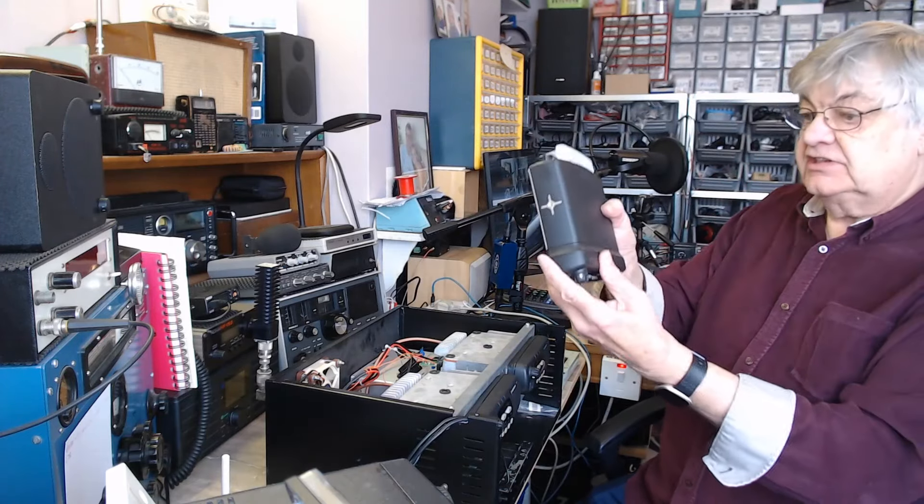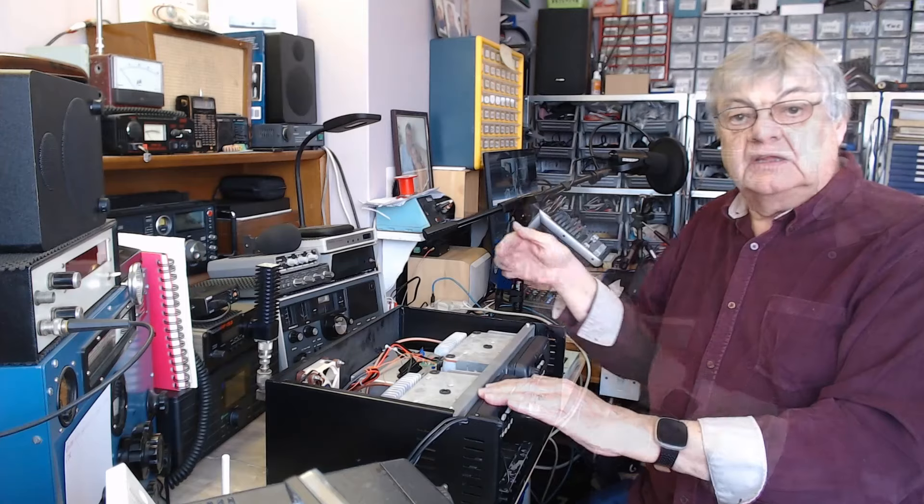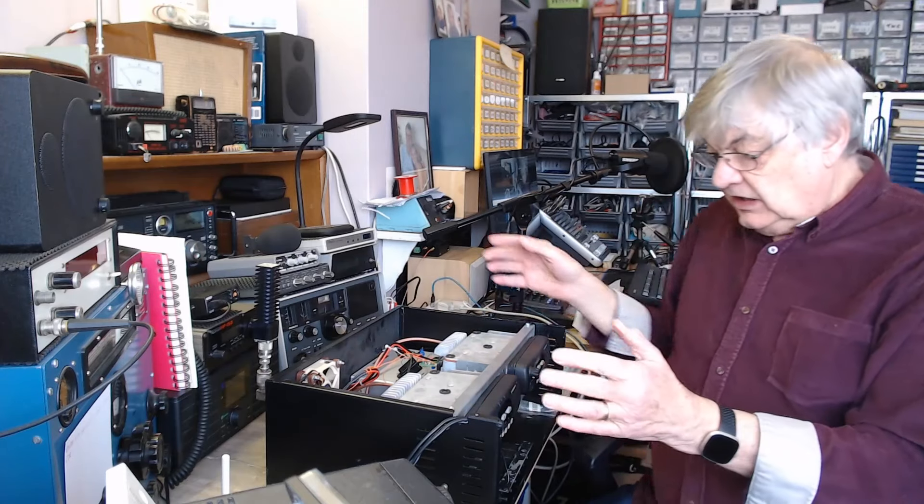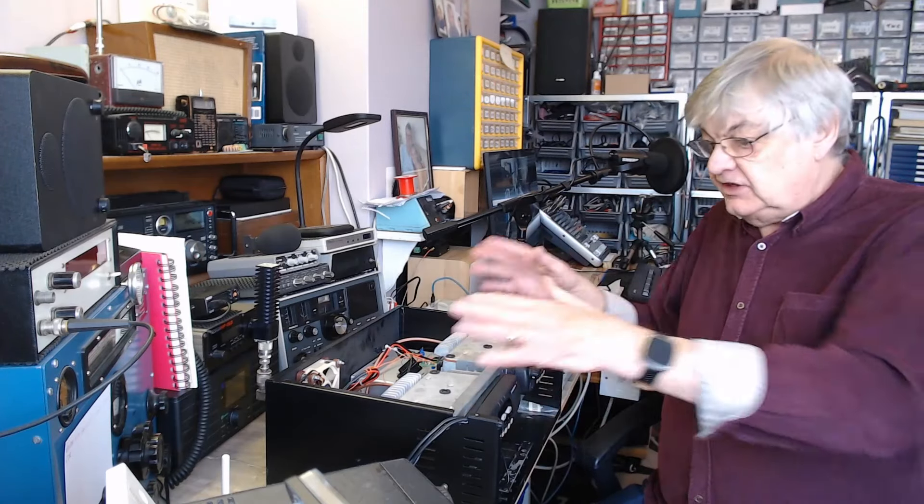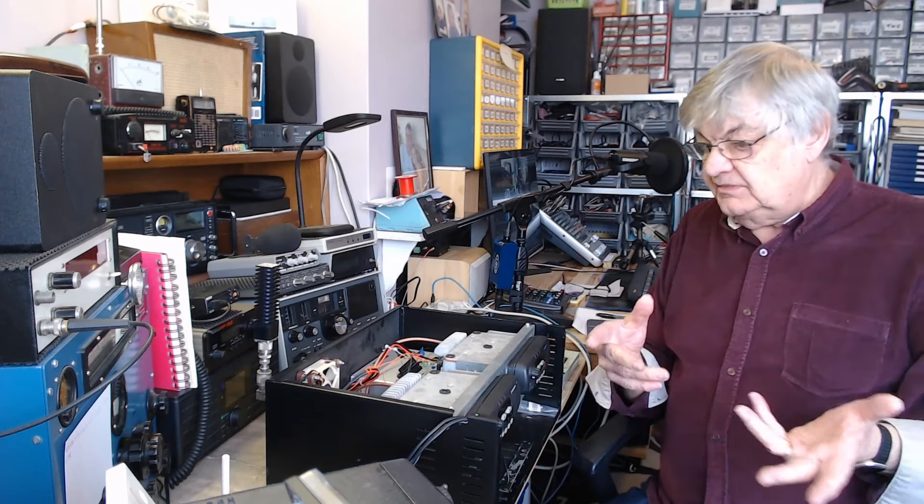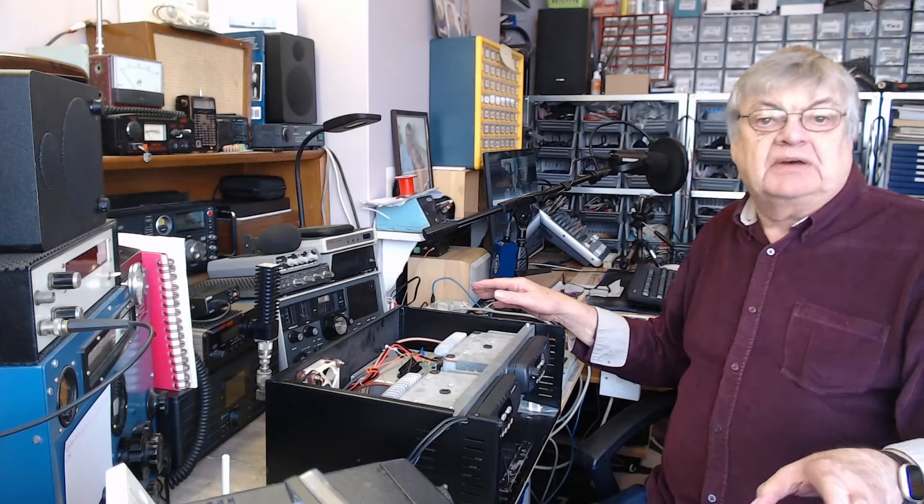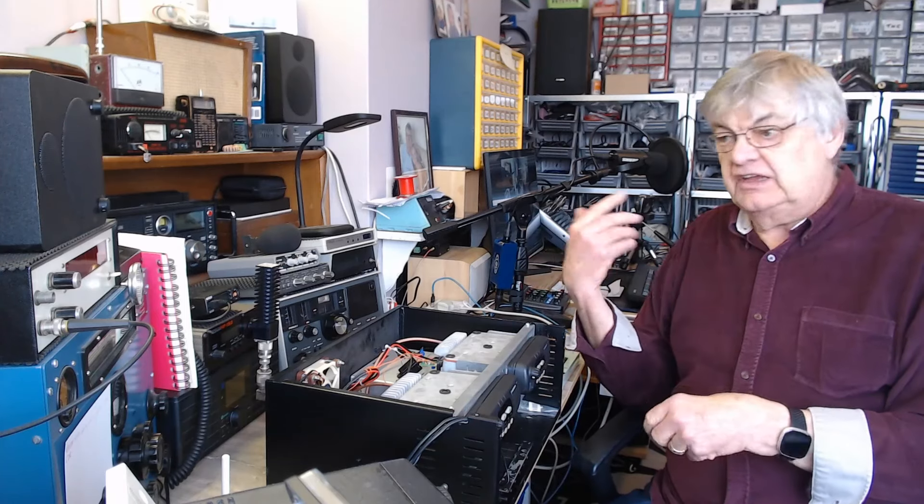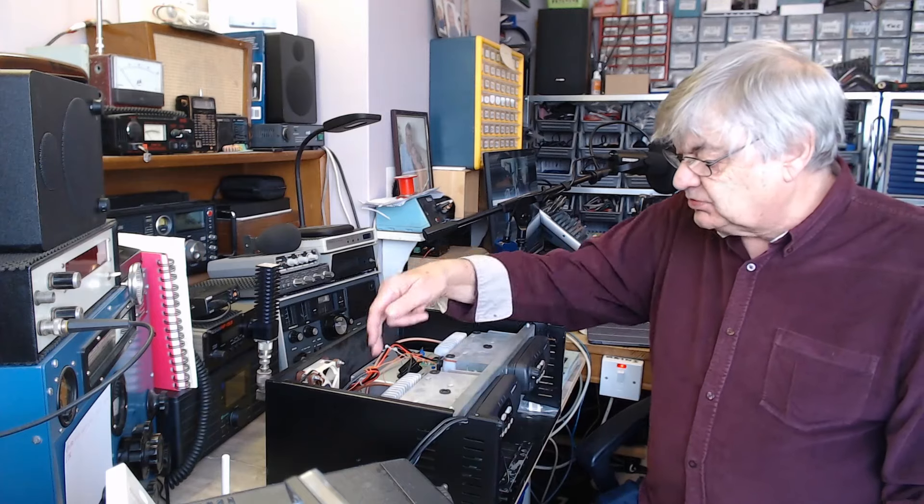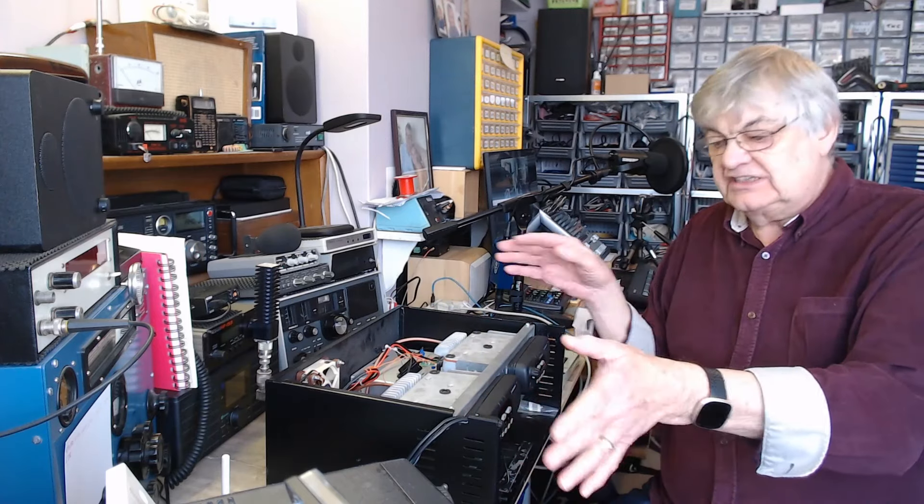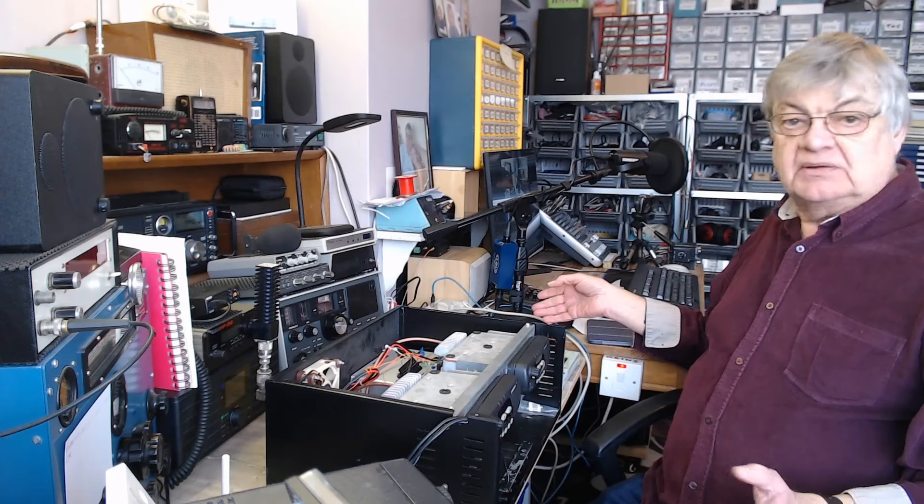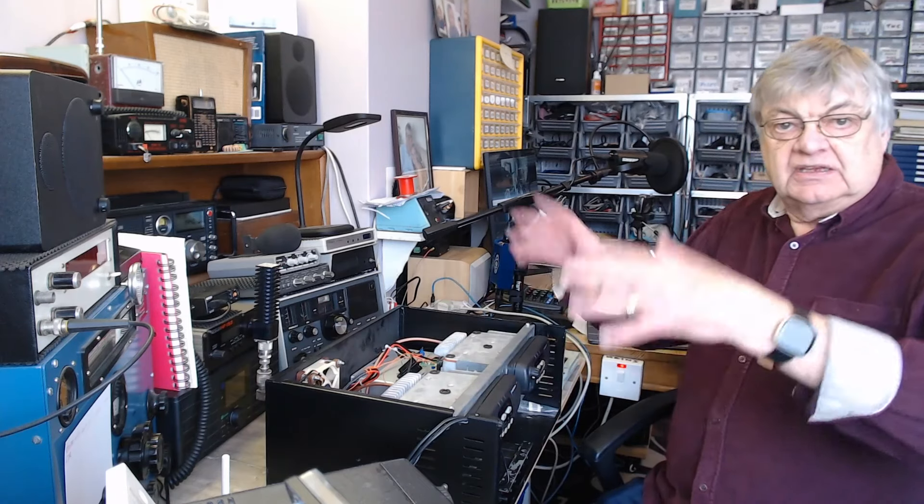This is just a spare one to show you the sense wire I mentioned. There's a power cut. This could be at a remote location somewhere, no one around to switch it back on. If there's a power cut, the thing powers down. You know like your computer, that's it, you've got to come and turn it back on. Well that sense wire basically turns it all back on again as soon as the power comes on. The whole thing kicks up and off it goes again.